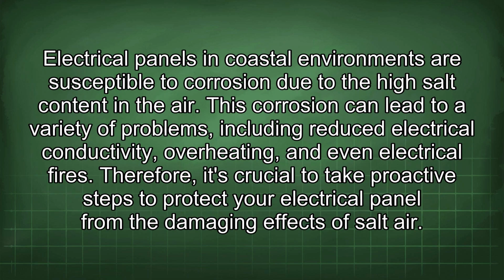Electrical panels in coastal environments are susceptible to corrosion due to the high salt content in the air. This corrosion can lead to a variety of problems, including reduced electrical conductivity, overheating, and even electrical fires. Therefore, it's crucial to take proactive steps to protect your electrical panel from the damaging effects of salt air.